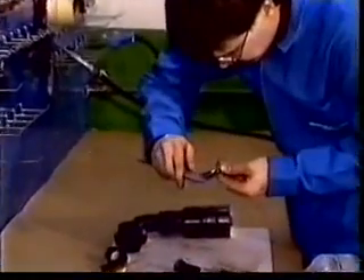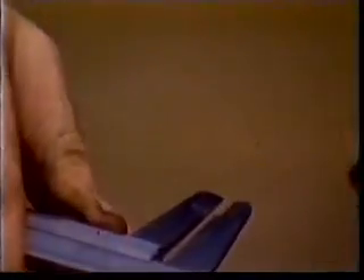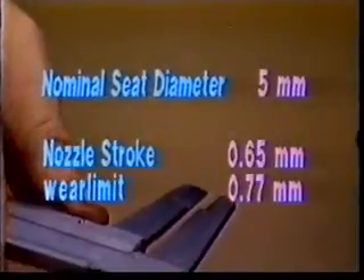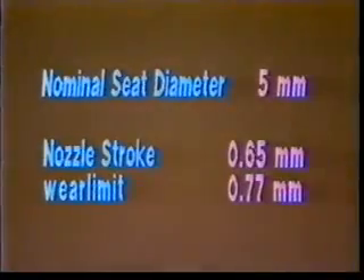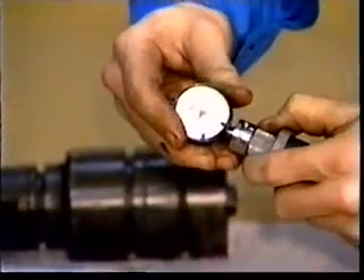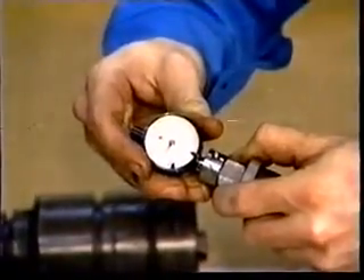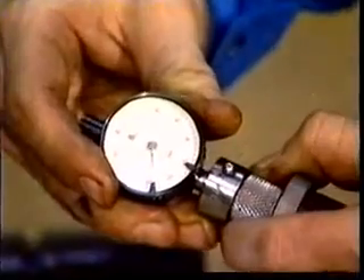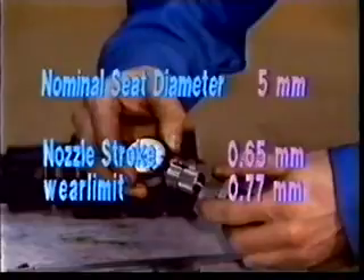Measure the uppermost needle seat diameter. The value must not exceed the nominal by more than 0.5 mm. The nominal seat diameter on a VASA 32 is 5 mm. Check the needle strokes of the nozzles which have been in use. A too long stroke may cause changes in the nozzle function, increase wear rate, and in the worst case even a broken nozzle tip. The nominal value of the nozzle stroke on a VASA 32 is 0.65 mm and the wear limit is 0.77 mm.